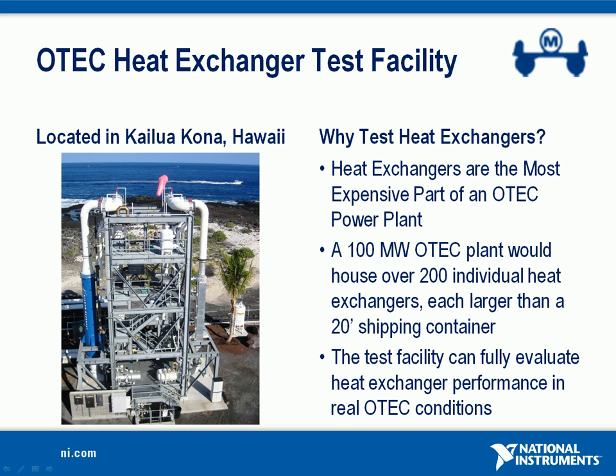Makai is currently addressing all of the heat exchanger design issues in our OTEC heat exchanger test program. We are performing corrosion testing in parallel to performance testing to determine optimal materials and manufacturing techniques for use in an OTEC heat exchanger. The facility shown in the picture is a 46-foot-tall structure capable of testing multiple heat exchangers in realistic OTEC conditions.